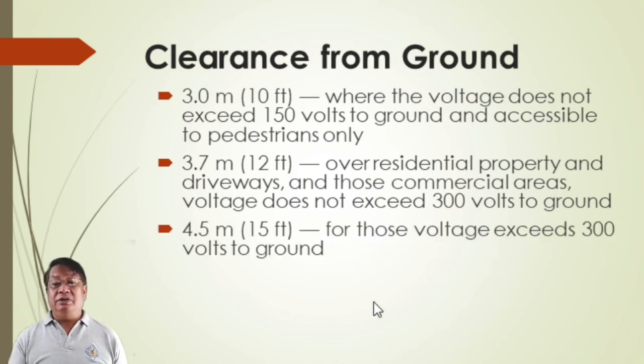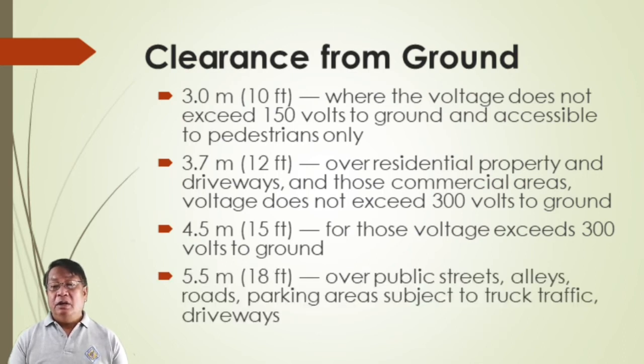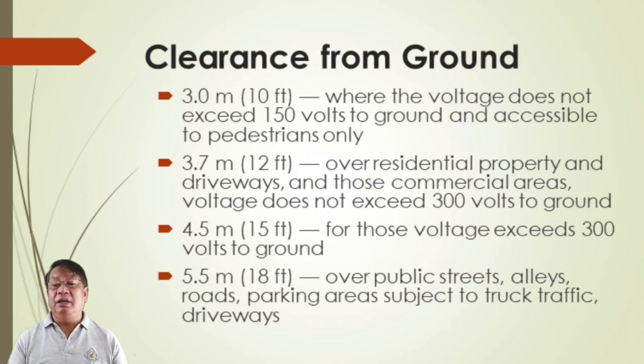Over public streets, alleys, roads, parking areas subject to truck traffic, and driveways, conductors should not be less than 5.5 meters or 18 feet; otherwise they will be damaged by trucks and other large vehicles. For conductors over track rails or railroads, maintain 7.5 meters or 24.5 feet.